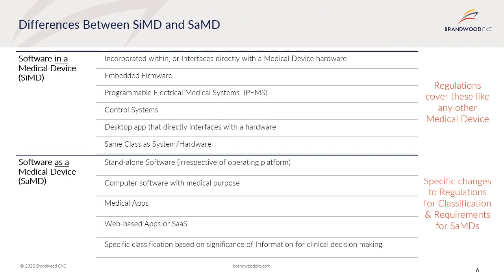Traditionally, medical device software was primarily referred to as software that was part of a host or parent device or hardware — that is, software in a medical device. With the rise of standalone software devices, a group known as software as a medical device has come about. Software in a medical device can be incorporated within or interface directly with medical device hardware. They can be embedded firmware, also known as programmable electrical medical systems referenced in IEC 60601-1 standard. They may be part of a control system or a desktop application that directly interfaces with a hardware device. They are usually the same class as the host or parent system, and are regulated like any other medical device, usually included within the host or parent device submissions.